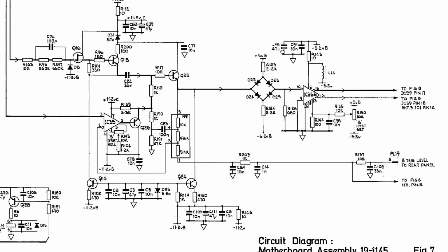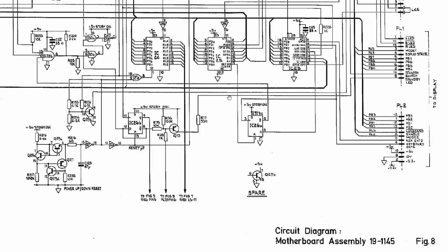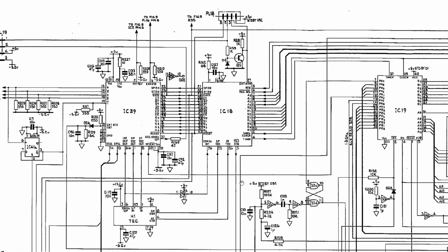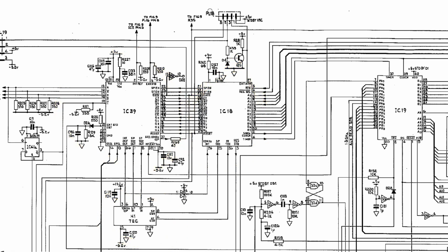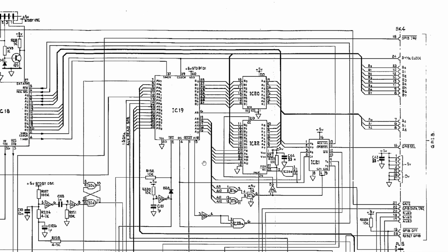The rest of the counter isn't particularly interesting. We can take a look at some of the stuff. Here's the counter chips. So there's a custom counter chip, completely secret, followed by another chip, I think, which is completely secret. And then they are tied together with this thing, which is a hybrid circuit. This is the little circuit that does, quote, timing correction. It looks at signals on these two chips, and I don't know, it sends signals to the second chip depending on things that happen in the first chip. And it makes it more accurate. Don't ask me how, but supposedly it makes it more accurate. And then finally it goes into a buffer that allows you to read it with a microprocessor.